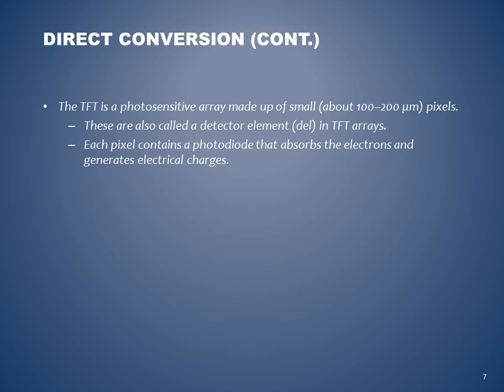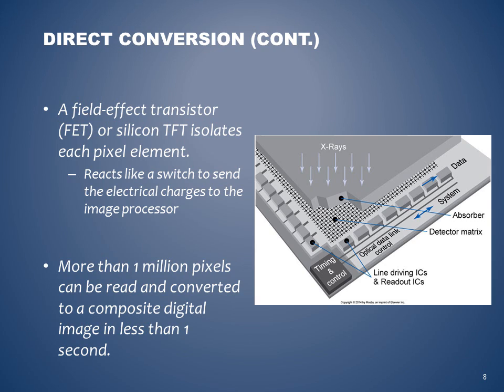The TFT is a photosensitive array made up of small, about 100 to 200 micron pixels. These are also called a detector element, or DEL, in TFT arrays. Each pixel contains a photodiode that absorbs the electrons and generates electrical charges. A field effect transistor, or FET, or silicon TFT, isolates each pixel element. It reacts like a switch to send the electronic signal, or charges, to the image processor. More than 1 million pixels can be read and converted to a composite digital image in less than 1 second.